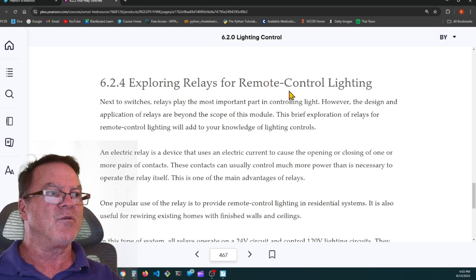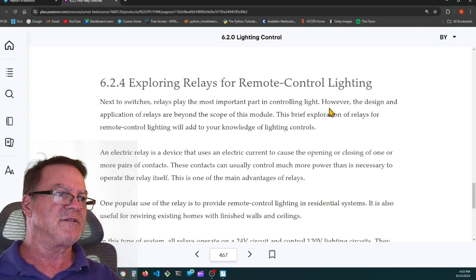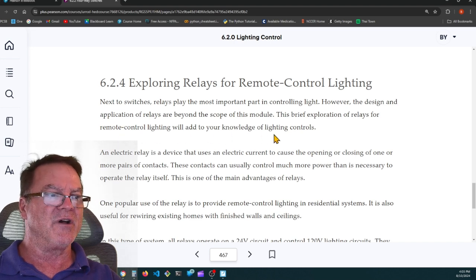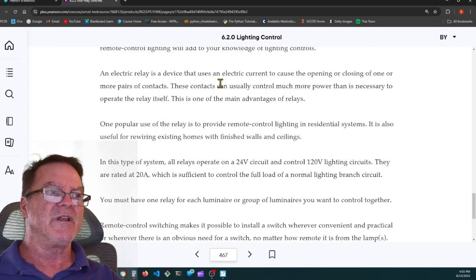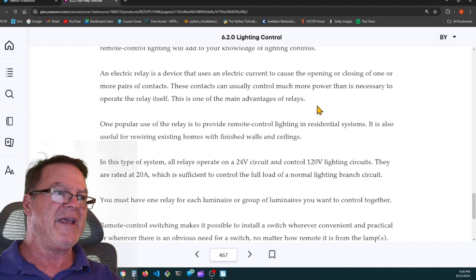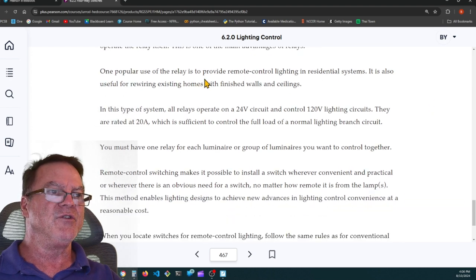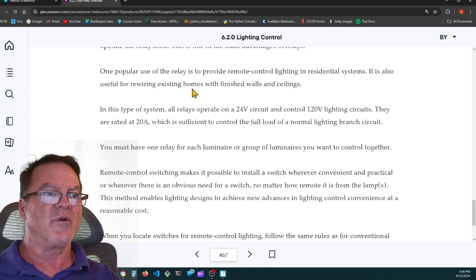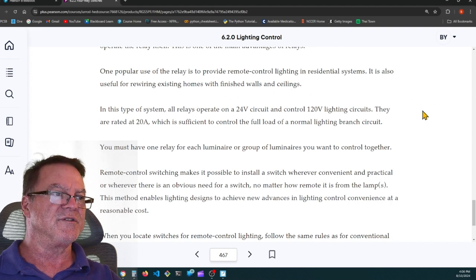6.2.4, exploring relays for remote control lighting. Next to switches, relays play the most important part in controlling lights. However, the design and application of relays are beyond the scope of this module. This brief exploration of relays for remote control lighting will add to your knowledge of lighting controls. An electric relay is a device that uses an electric current to cause the opening or closing of one or more pairs of contacts. These contacts can usually control much more power than is necessary to operate the relay itself. This is one of the main advantages of relays. One popular use of the relay is to provide remote control lighting in residential systems. It's also useful for rewiring existing homes with finished walls and ceilings.